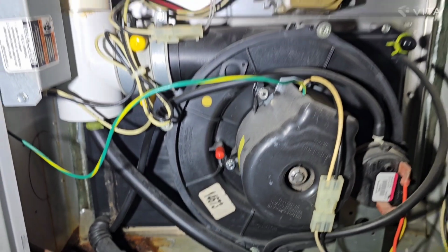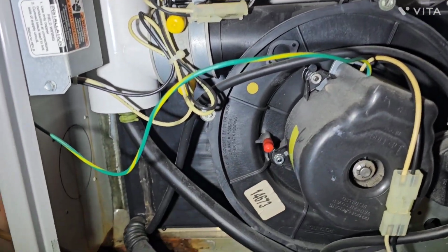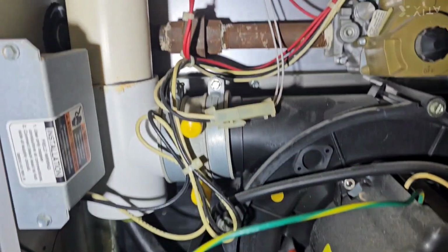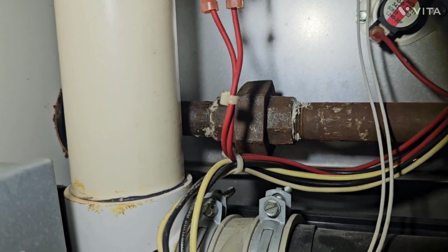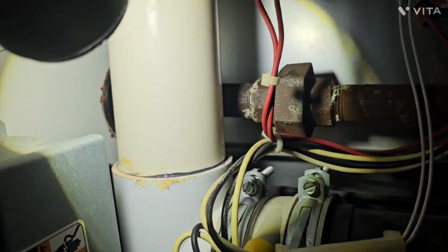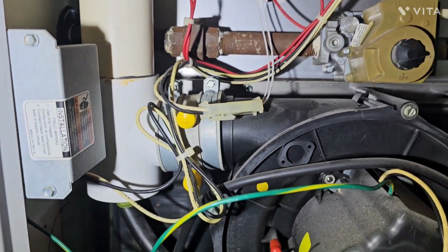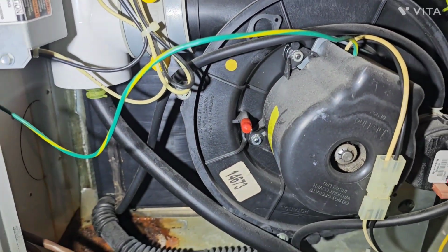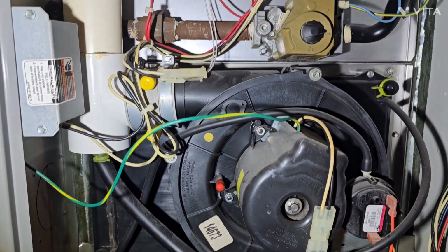So it's really a good idea to pull the cover off periodically, check your furnace, and make sure the leaks are stopped. Sometimes it's as simple as tightening up a clamp. Other times the glue joint has come loose, and I think it might be the case here. I can see some water around here, so it might be something you have to call a plumber for. Probably is, but you should check it every now and again.